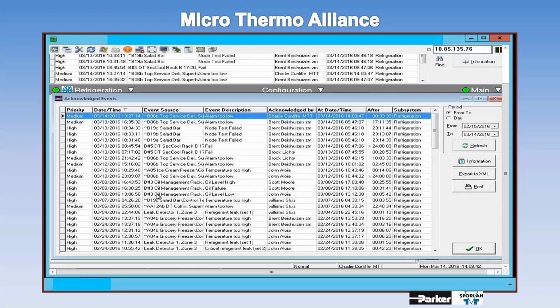Another report is called Alarm Acknowledgement, or Acknowledge Events—we call alarms events. Same as before, you can narrow in the time period: one day, one week, one month, one year. It tells you the priority of the event—high, medium, okay, or just notification—the date and time, the source of the alarm, a description, if somebody acknowledged it, who did the acknowledging, at what date and time, and what subsystem they were working in.